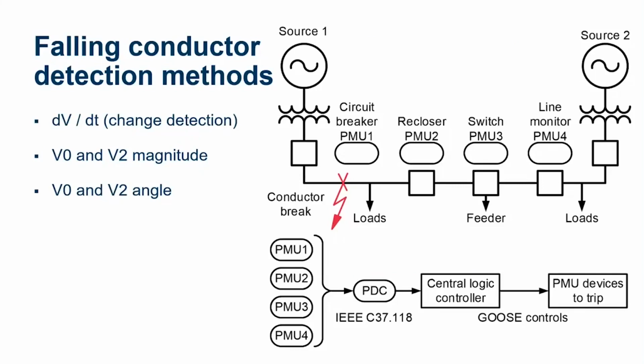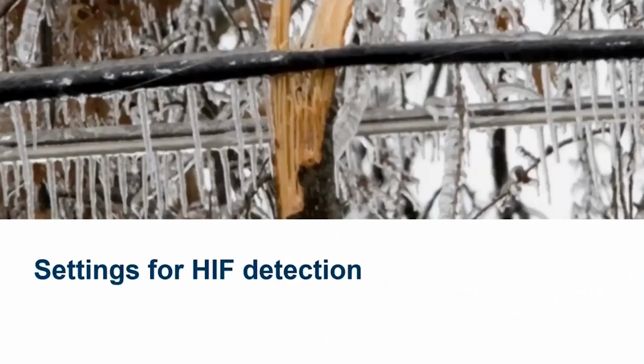One of the challenges with this system is that it's very robust, but it requires implementation as a complete system. This has to be done all at once, and we have to have PMUs at each end of each protected line segment in order for this to be successful. Very interesting application. If you have additional interest, I would recommend checking out the paper on the SEL website, which has additional information on this particular scheme.